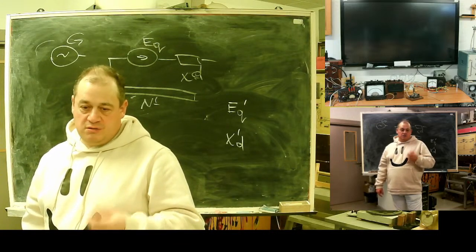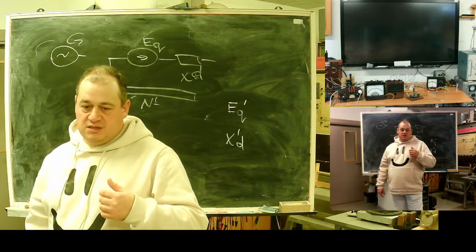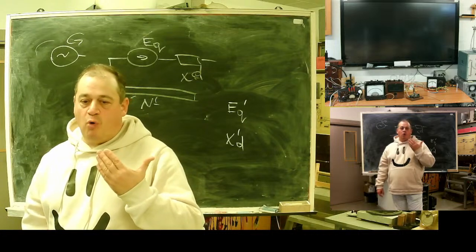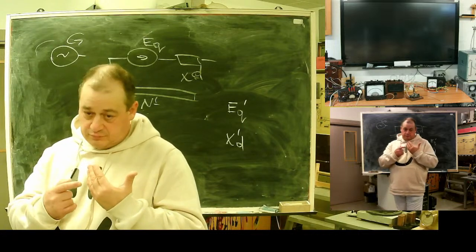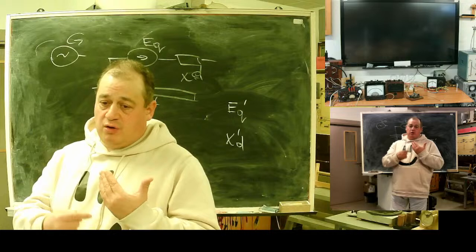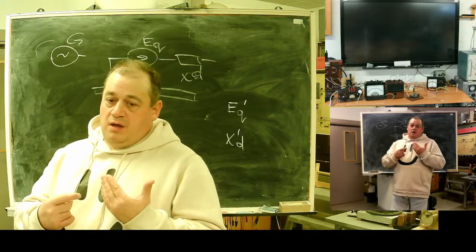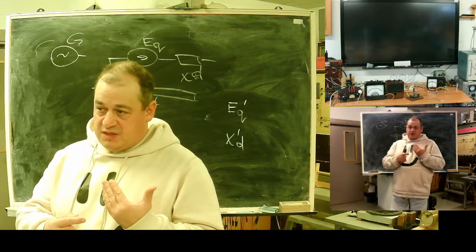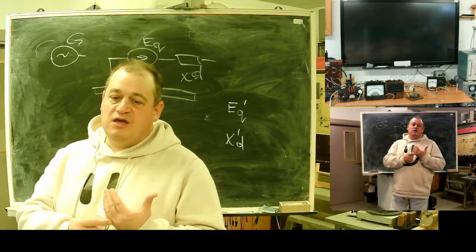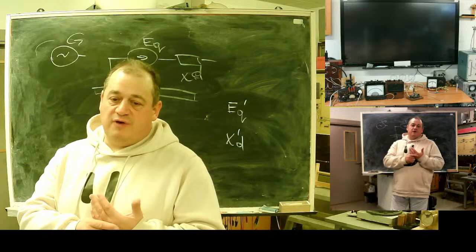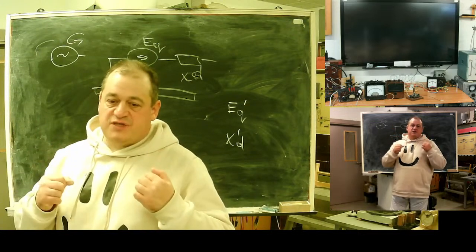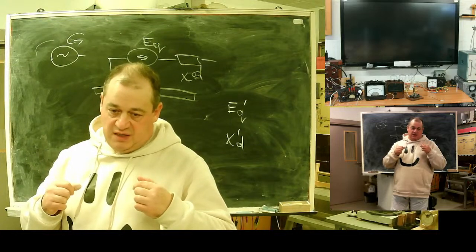On large hydro generators, front surfaces of the poles are made with special grooves, special cut-ins for the short circuit winding. And very massive copper rings are placed here.